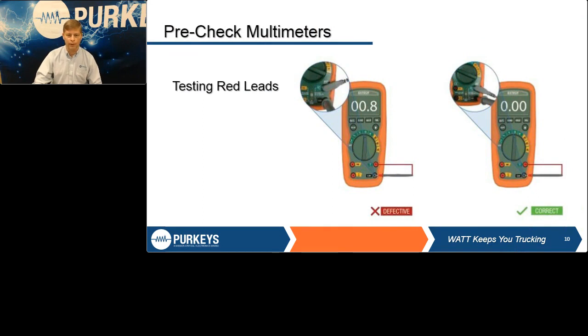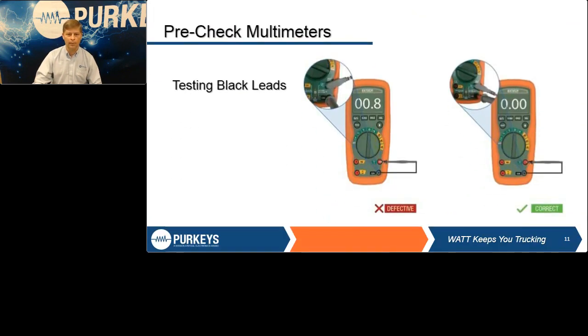We're going to put the one end back in the meter like it belongs, and we're going to take the tip of the lead and put it where the black lead would go, and we're going to check it. If it zeroes out, it says, hey, your red lead's good. We can do the exact same thing with the black lead. All we're trying to do is isolate it. Do I have a meter problem? Do I have a lead problem? What is it? What do I need to address?